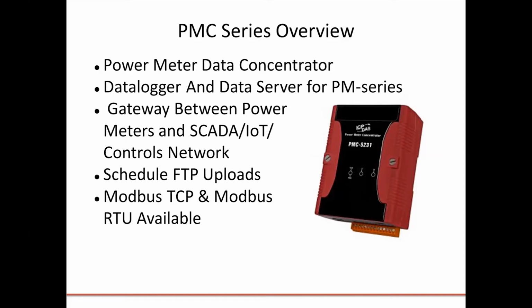They offer RS-232, RS-485, and Ethernet communication, and each data concentrator can be connected to up to 24 power meters per module. And they are designed specifically to work with our power meters, so setup and configuration is easy. They support email and SMS alarm functions, and you can regularly schedule FTP uploads of your logged data in addition to accessing real-time data through the module.